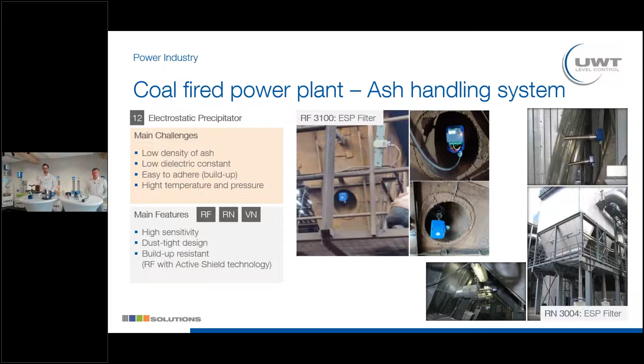Next one, we still stay with the ash handling system. We have a main challenge here in this pneumatic transfer pump, that we have light material. We have a low dielectric constant. Also, it's very easy on the unit itself to have a build-up, and we have temperature and pressure again, and it's a small silo. And when it comes to small silos, we also have the topic of vibration, and for two units we have the possibility to go for a separate housing. So with the RF, we can order it with separate housing, so that puts the electronic part away. And also with the VN 1256, we have the possibility to put the electronic part away, even when you have some vibration or higher temperature, because the housing can only hold 80 degrees, and we need to make sure that the housing is away from the temperature.